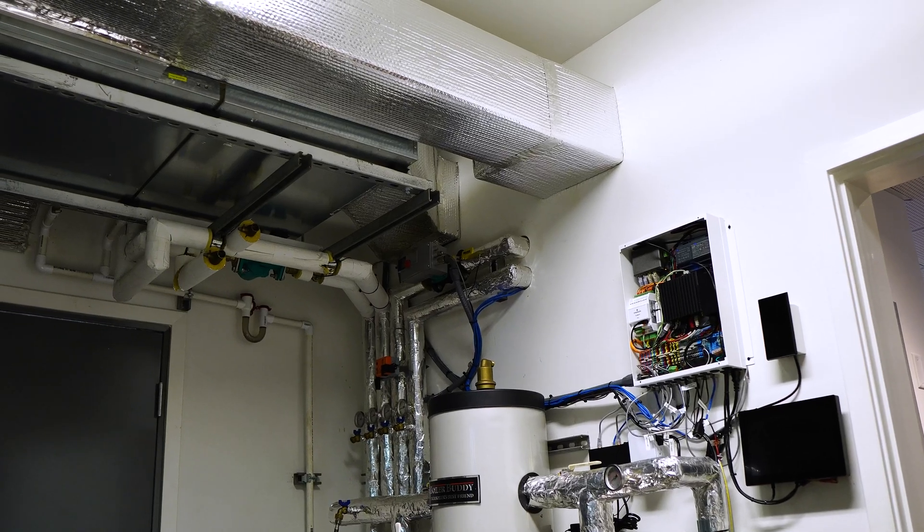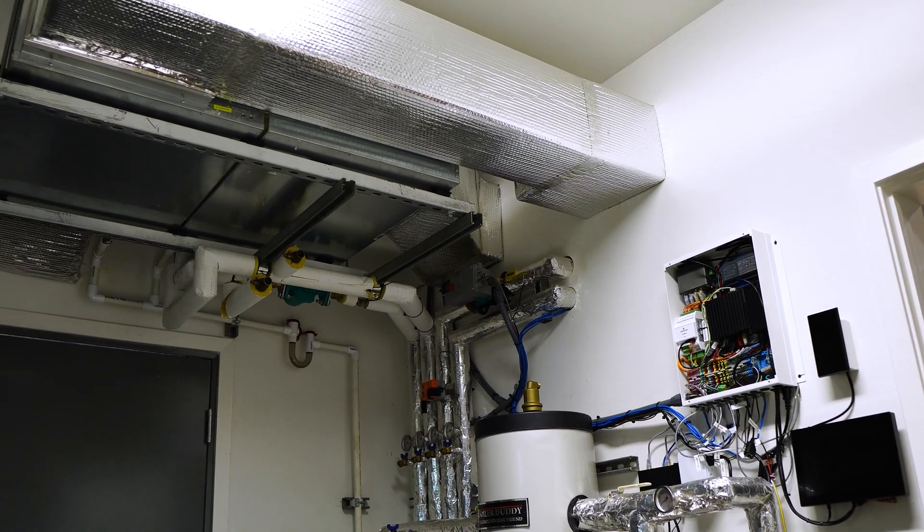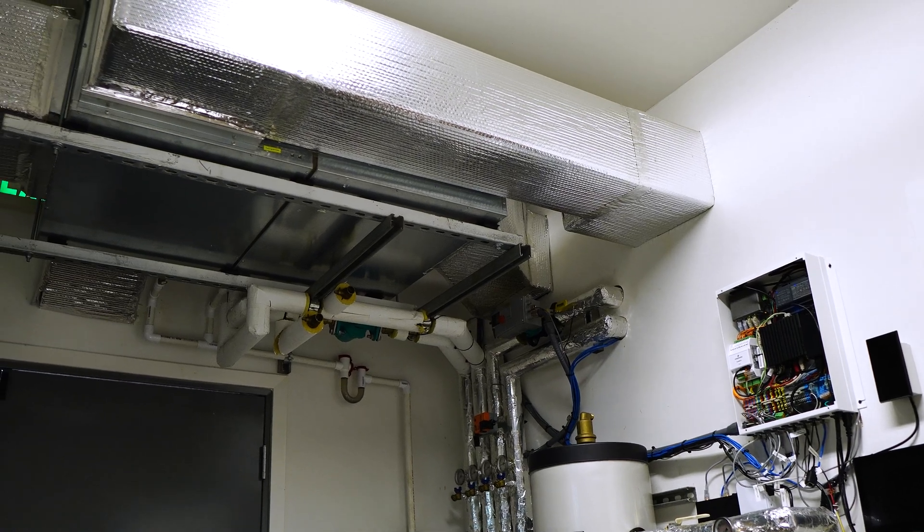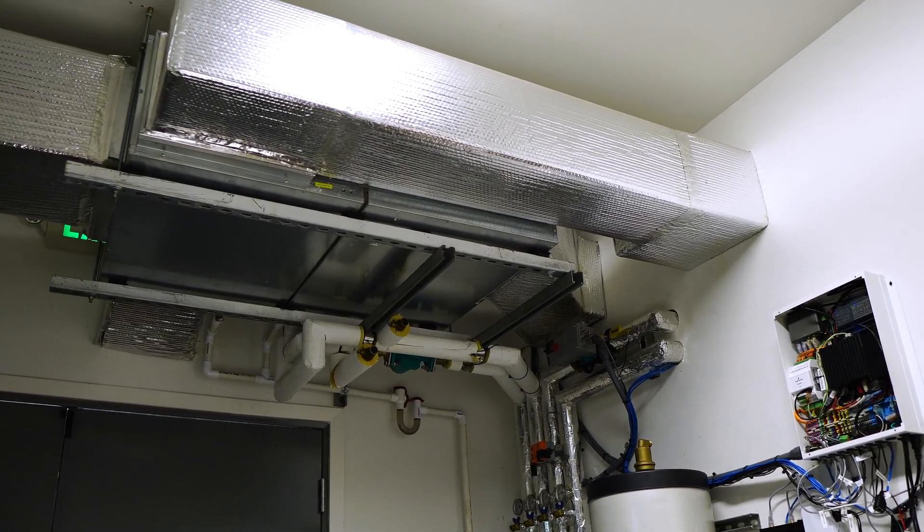With operative temperature and relative humidity, we can calculate the dew point temperature, so that's how we know what's going on in every zone of a home. The last thing that the mSenseRoom comfort sensor monitors is VOCs—volatile organic compounds—which reflect the indoor air quality of your space. We can use that data to activate forms of mechanical ventilation to ensure you're breathing the best air possible.